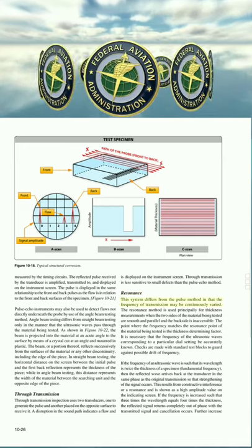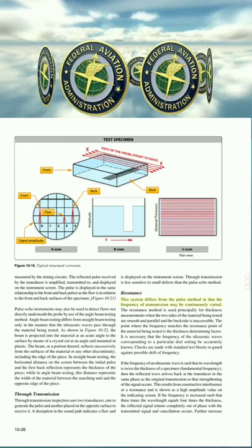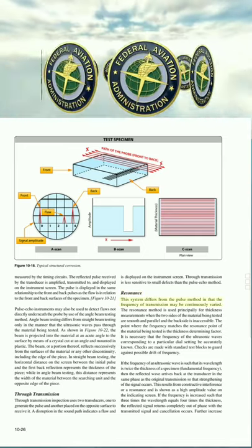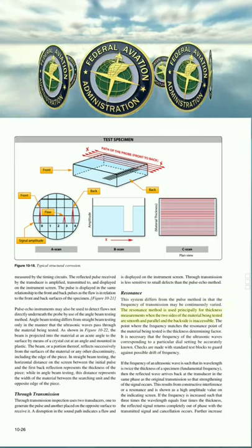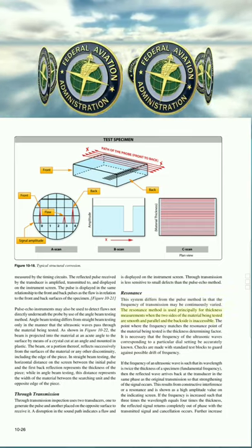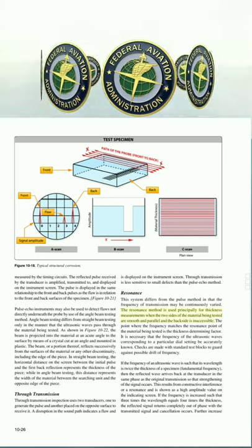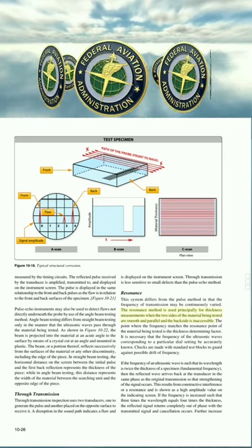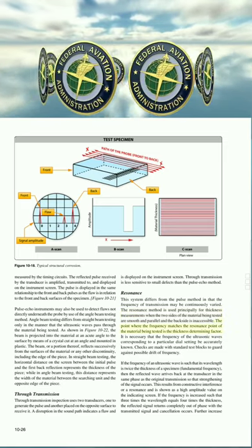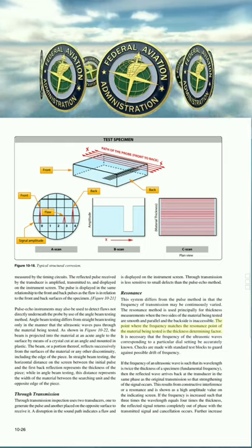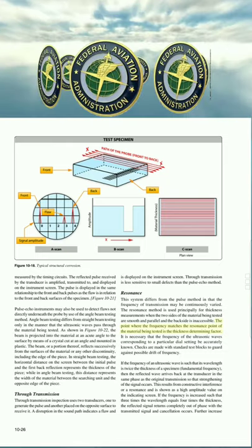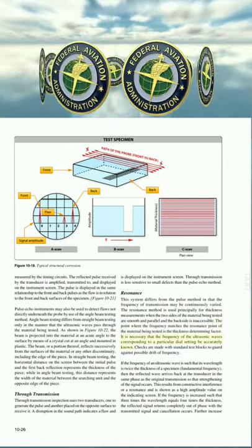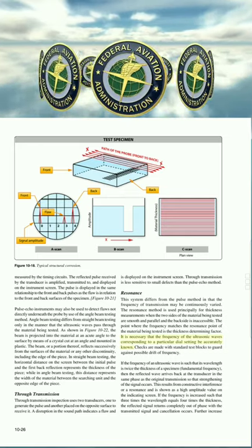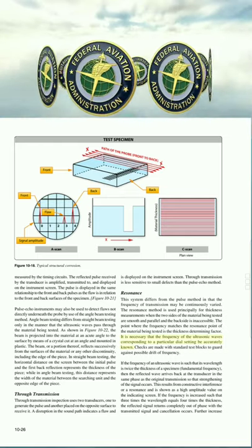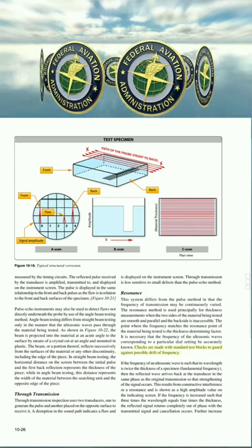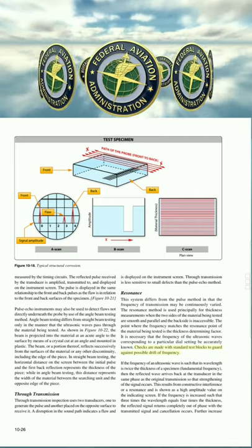Resonance. This system differs from the pulse method in that the frequency of transmission may be continuously varied. The resonance method is used principally for thickness measurements, when the two sides of the material being tested are smooth and parallel, and the backside is inaccessible. The point where the frequency matches the resonance point of the material being tested is the thickness determining factor. It is necessary that the frequency of the ultrasonic waves corresponding to a particular dial setting be accurately known. Checks are made with standard test blocks to guard against possible drift of frequency.